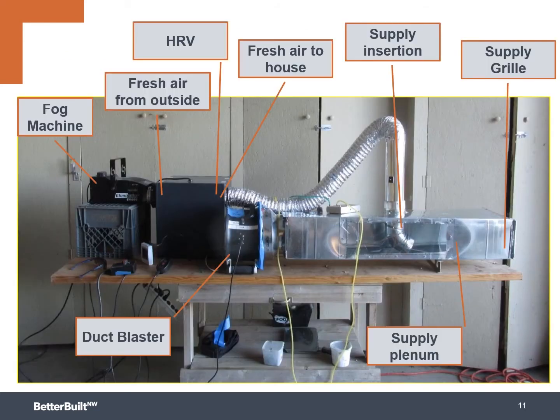Our team has actually done some experimenting to make sure that this integration into the supply side will actually work. So you can kind of see this supply insertion in a demonstration product that we built. What ends up happening is, much like a rock in a river, there's a little kind of safe space, right? The eddies and whirls in the river that go around the rock create a little pocket of less turbulence. And that's what happens when this elbow or injection port is put into the central air handler. This allows our fresh air from our heat recovery ventilator to blend and mix quite well into a little pocket of less turbulent air. And then the entire system will pick that up and deliver it throughout the house.